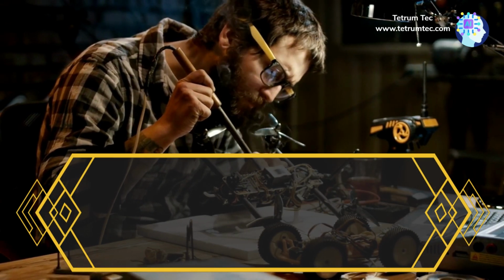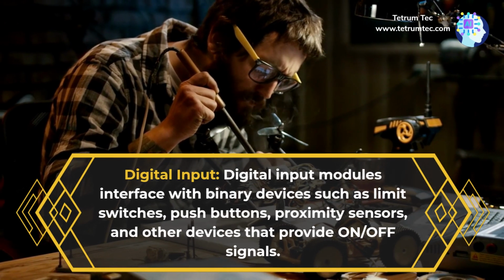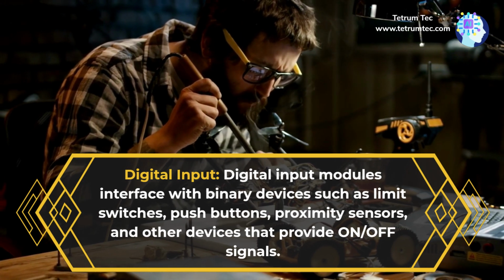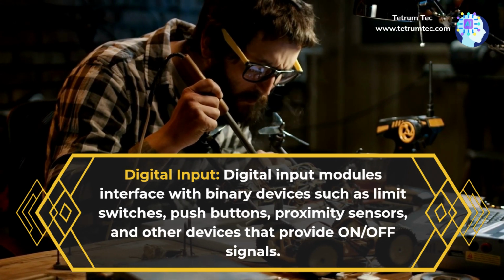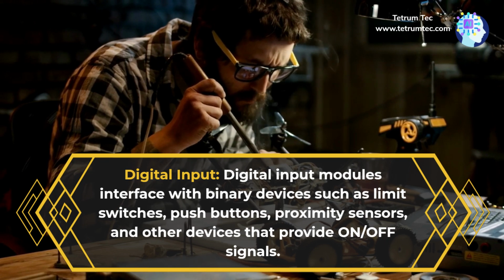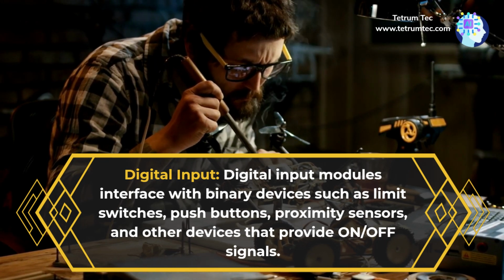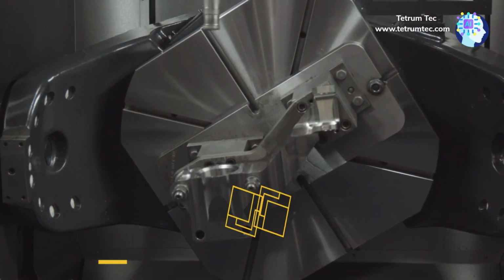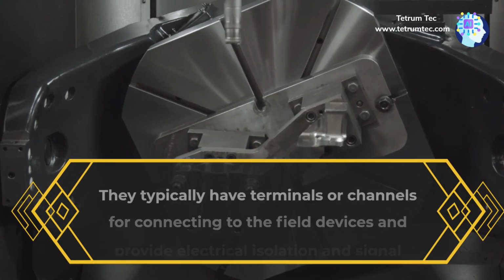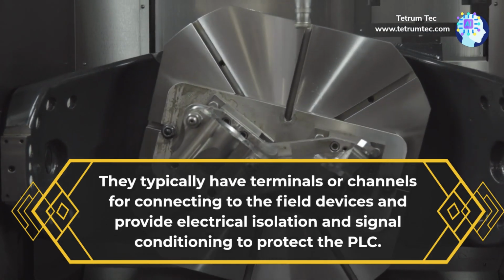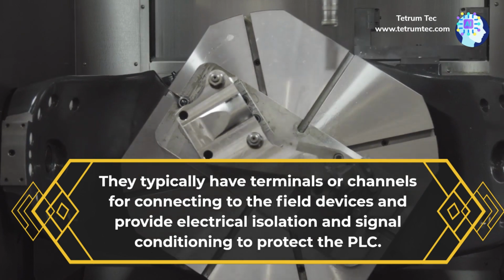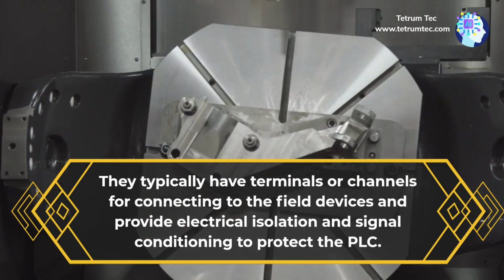Digital input. Digital input modules interface with binary devices such as limit switches, push buttons, proximity sensors, and other devices that provide on/off signals. They typically have terminals or channels for connecting to the field devices and provide electrical isolation and signal conditioning to protect the PLC.